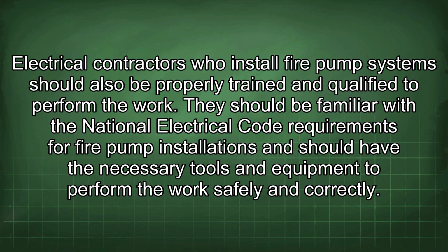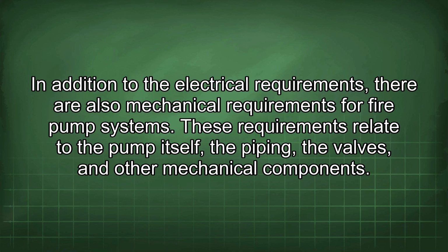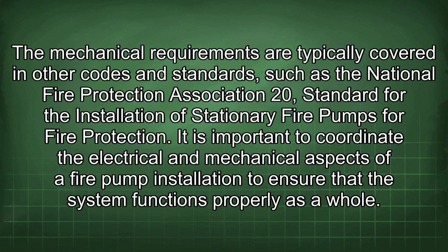Electrical contractors who install fire pump systems should also be properly trained and qualified to perform their work. They should be familiar with the National Electrical Code requirements for fire pump installations and should have the necessary tools and equipment to perform the work safely and correctly. In addition to the electrical requirements, there are also mechanical requirements for fire pump systems. These requirements relate to the pump itself, the piping, the valves, and other mechanical components. The mechanical requirements are typically covered in other codes and standards, such as the National Fire Protection Association 20 standard for the installation of stationary fire pumps for fire protection.